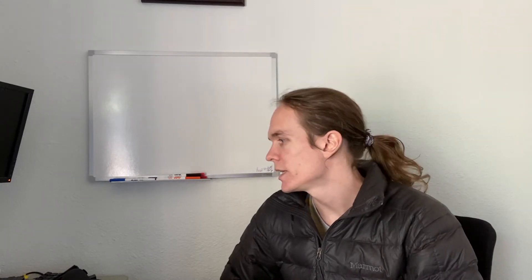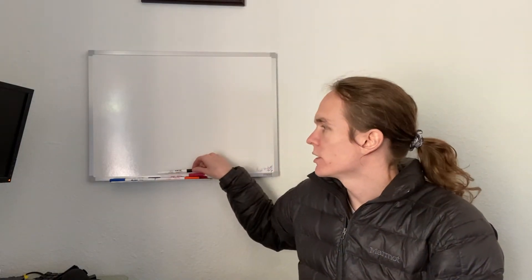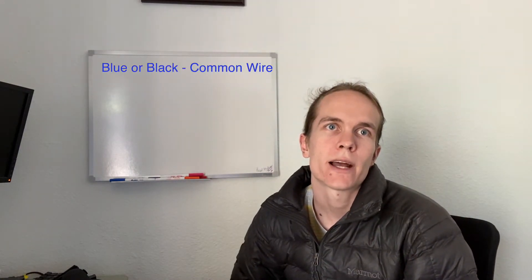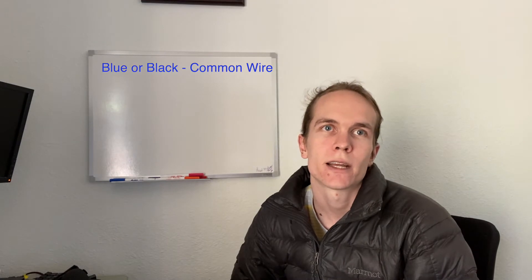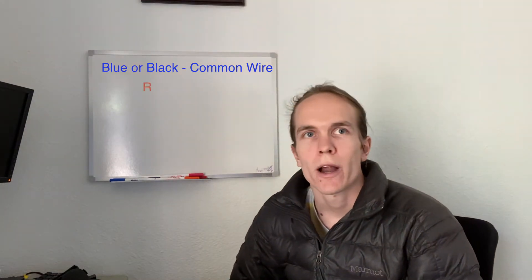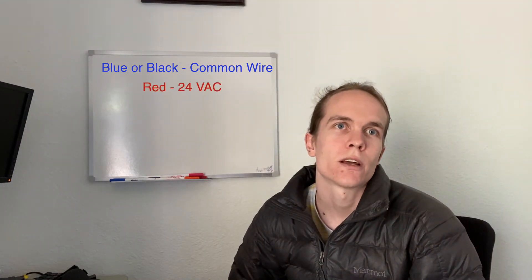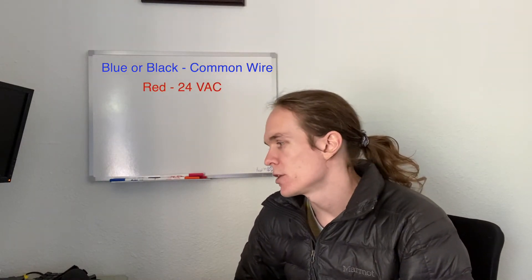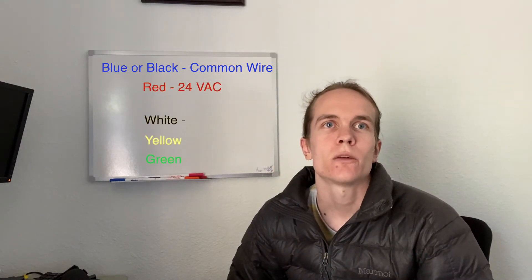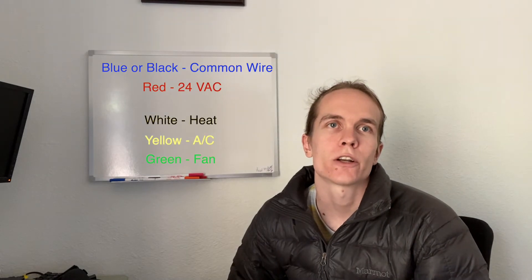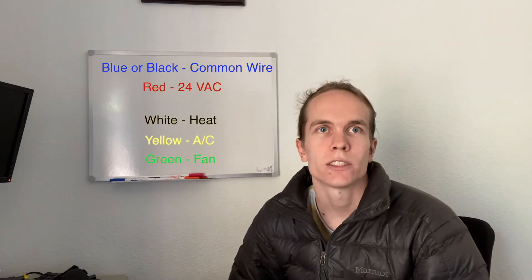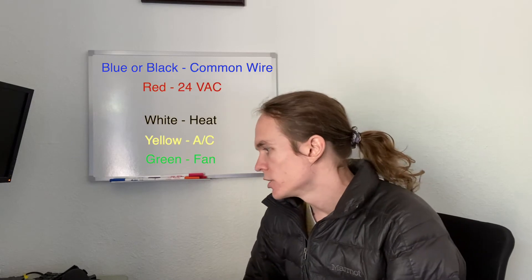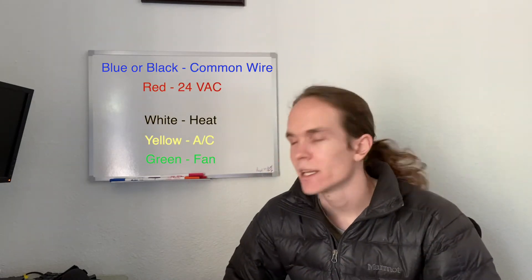The first wire that you're going to do is going to be your blue or black wire. And that's going to be your common wire, better known as the C wire for HVAC. The next wire is going to be your red wire, which is going to be your 24 volts AC current wire. And then your green, white and yellow, those are going to be your signal wires to turn on your different systems. Green is your fan, yellow is your AC, and white is your heat.